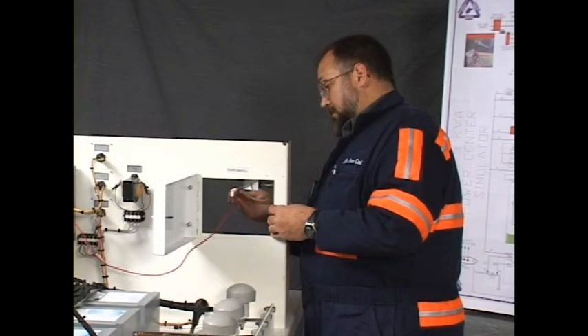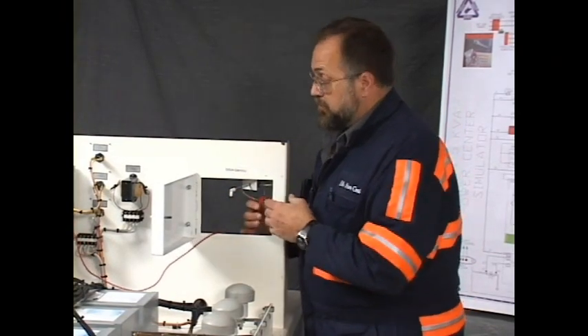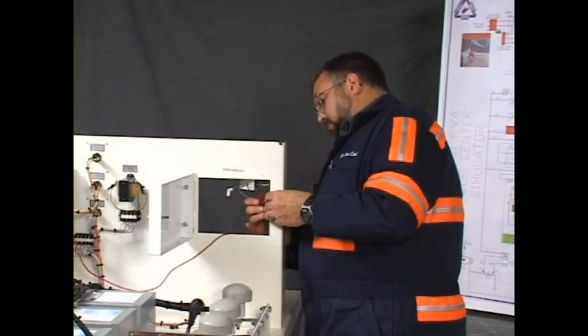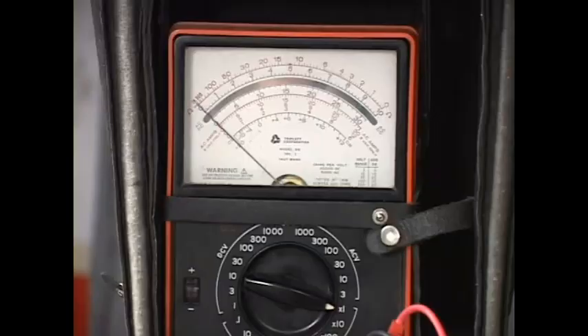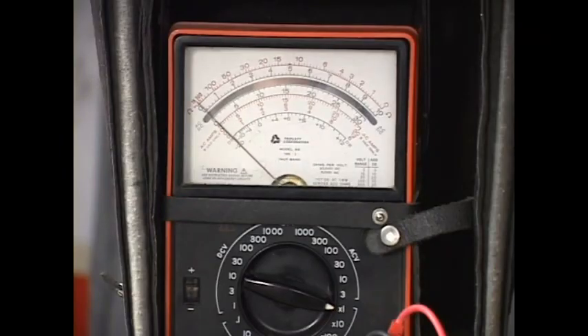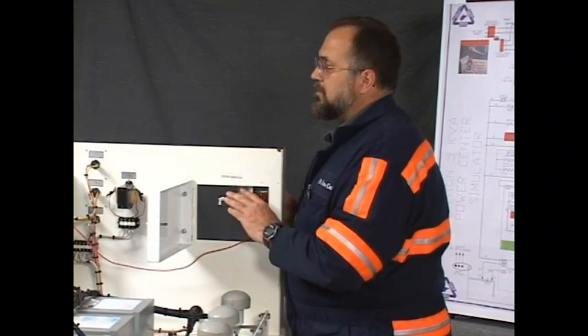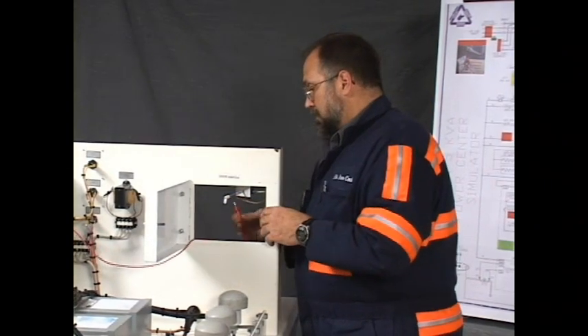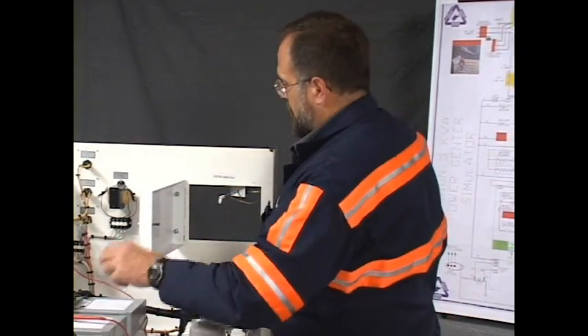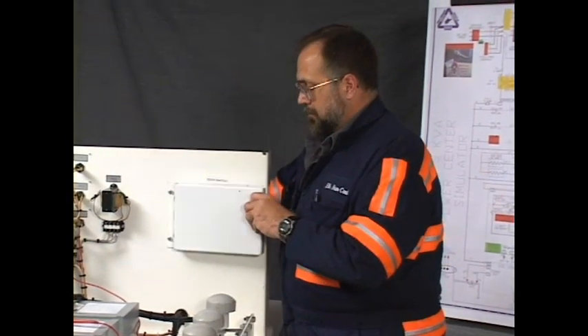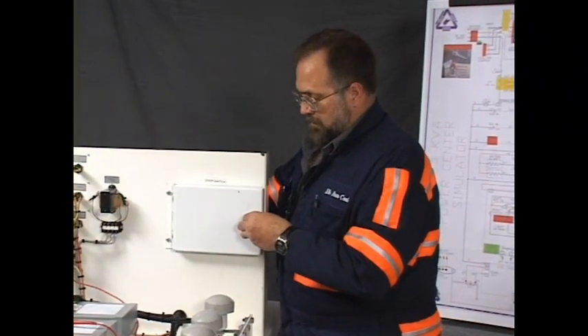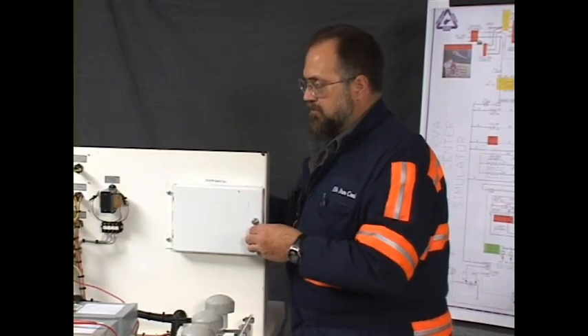Now, the door is open and the switch should be open. I'm going to read across the switch while we're here, to show you the operation of the switch. As you can see, it's open. Now, when I close the door, it would close the switch. Note the meter reading. The meter shows a closed circuit, shows continuity through the switch. Got a little resistance there though, not much. All right. That is as the circuit should read.